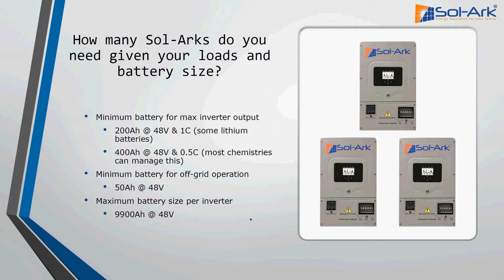Here are some specs for how big of a battery you need to make the most of a Sol-Ark 12K or 8K inverter. The minimum battery size to get the maximum continuous output from the inverter, whenever you're only going off battery, is about 200 amp hours of lithium, as long as you can discharge at 1C. 1C refers to the capacity of the battery bank, so 1C of a 200 amp hour battery is 200 amps of continuous discharge. But not all batteries or BMSs can do that. Another example: if you had a 0.5C, or half the capacity discharge rate, then 400 amp hours will get you the most out of the system.